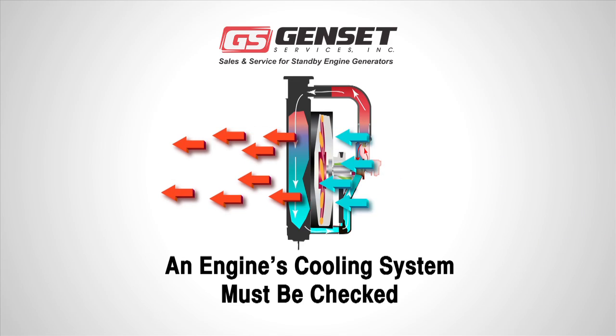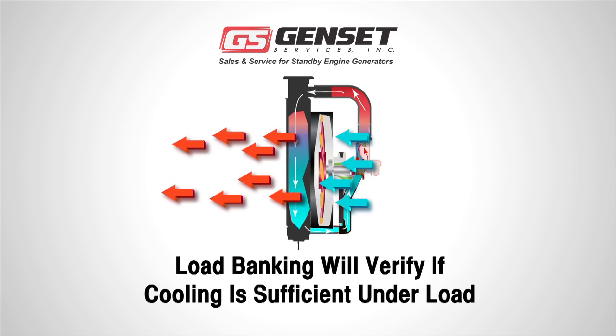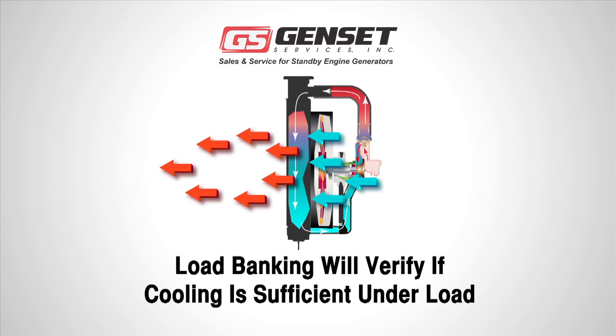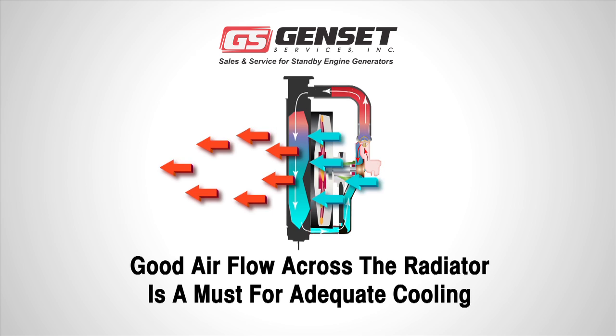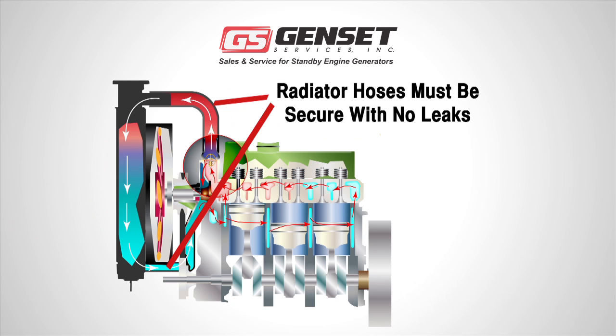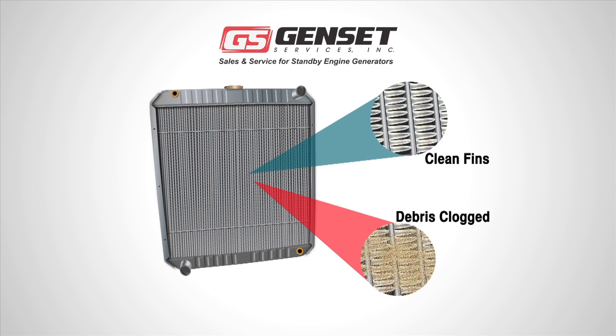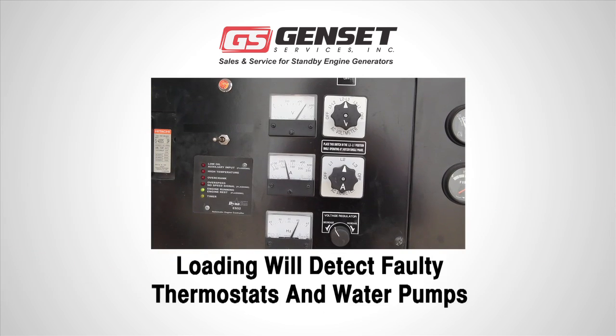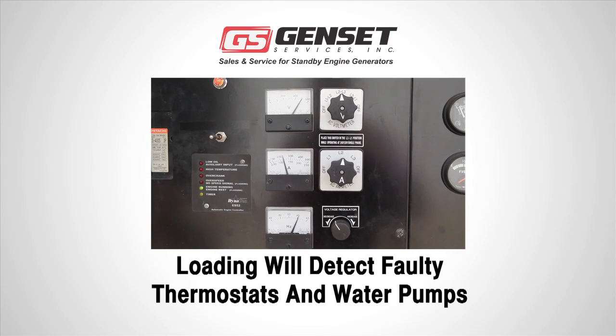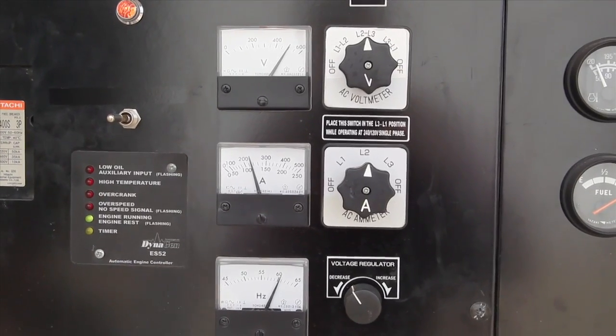Another cause of underperformance is problems with an engine's cooling system. Load banking will verify if cooling is adequate for the generator to carry the load without overheating. Airflow over the radiator is critical for cooling. Most common problems with cooling are loss of coolant due to radiator leaks and faulty hoses. Also, radiator fins can become blocked with debris, which will significantly reduce airflow and the radiator's cooling ability. With the engine, cooling issues, such as a faulty water pump or faulty thermostat, will be identified if insufficient cooling is detected during the load bank test.